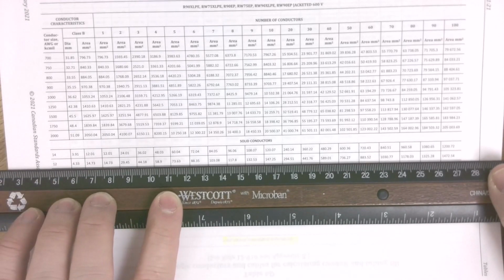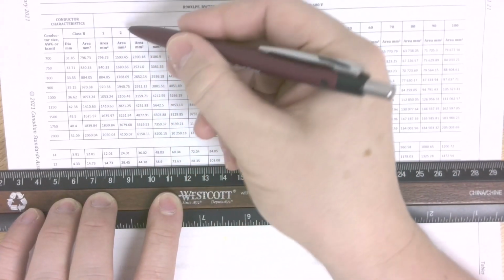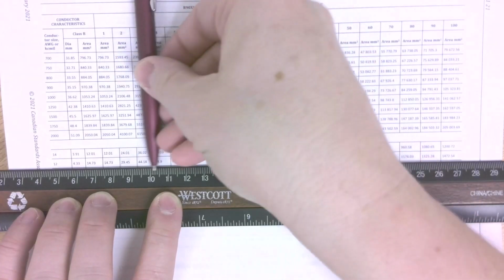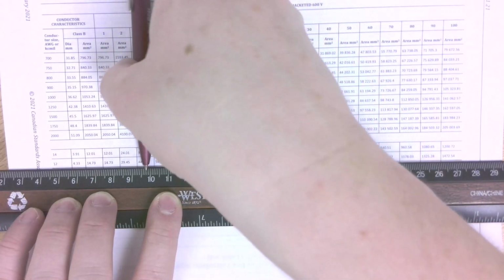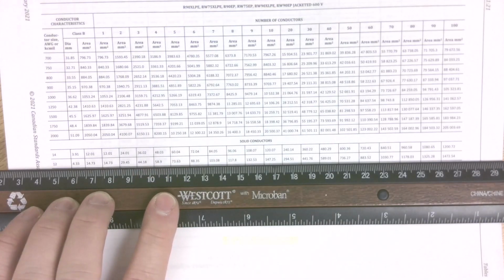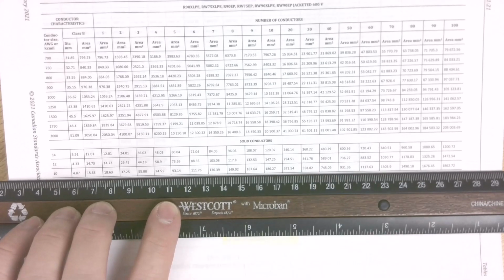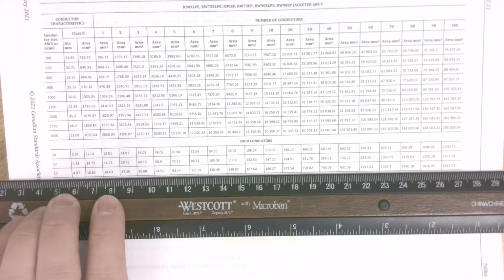And so there's two ways to do it. I could just take this 2, which I'm going to do for this one. It has 2, and I'll just maybe put a pen there to make sure. Okay, yeah, 2 12 gauge from table 6C are 29.45 millimeters squared. Then I have 4 10 gauge, and I'm just going to do it a little bit different to show you the other way, but it's pretty straightforward. I'm going to do 4 times 18.63.